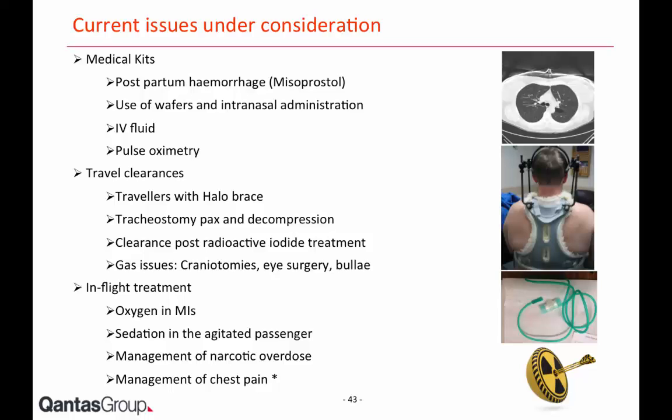We thought about, well, do they chop off the mask and just put the inlets there? That still probably wouldn't be high enough flow rate because you've got no form of reservoir. So they probably need to use one of these types of adapters if they really want to be covered for a rapid decompression, which are extremely rare again, but do actually happen. So we're actually looking at maybe trying to find someone that could do a study to actually analyse this issue. So it's just very minutiae, but it's the sort of thing that we get asked about.